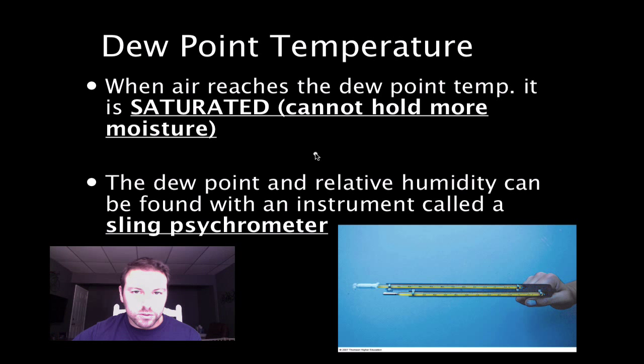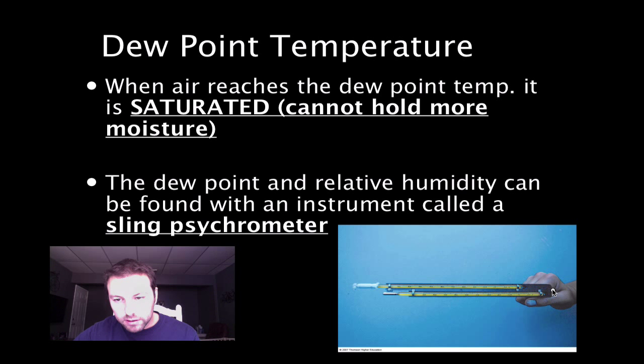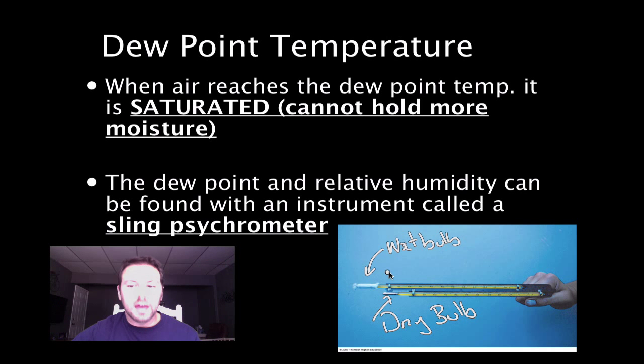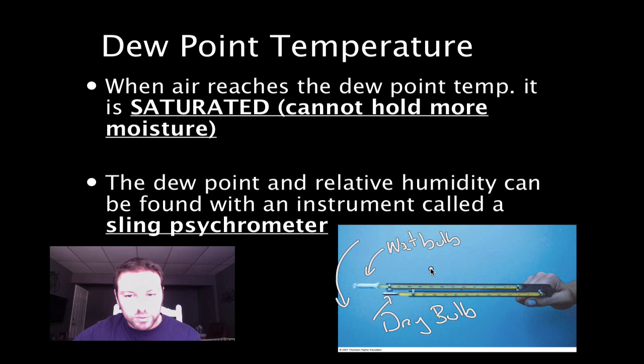We can find the dew point temperature using what's called a sling psychrometer. The sling psychrometer has a little handle and two thermometers on it — a wet bulb and a dry bulb. The wet bulb has a little cotton gauze that gets wet, and then you sling the whole thing around. By finding the difference in temperature between the wet bulb and dry bulb, we're able to find the dew point temperature using a chart in our reference table.